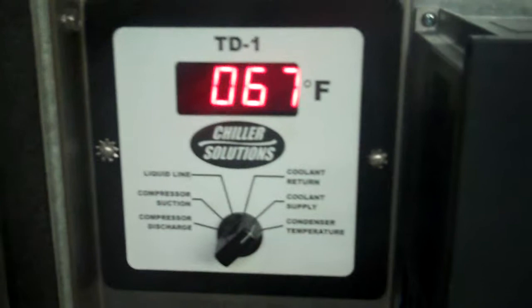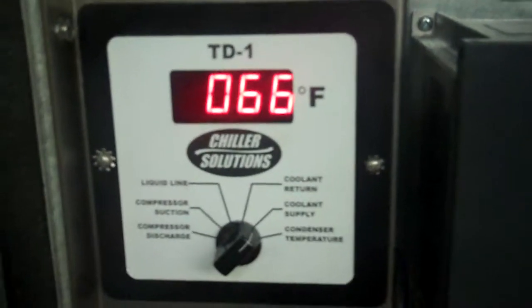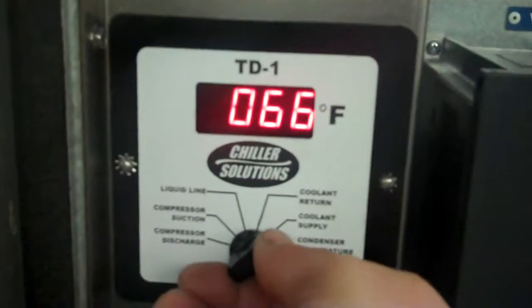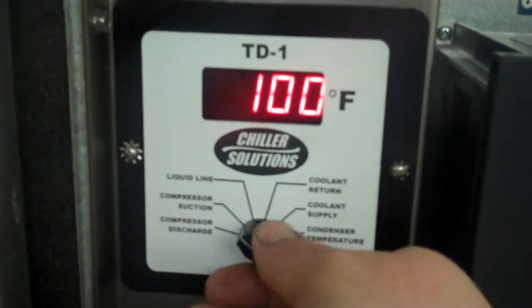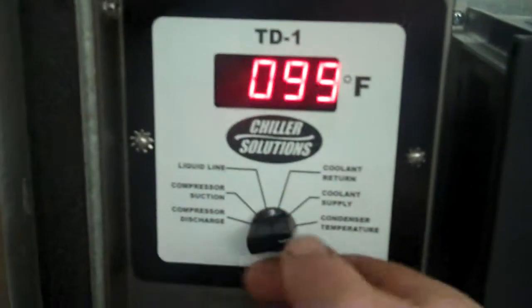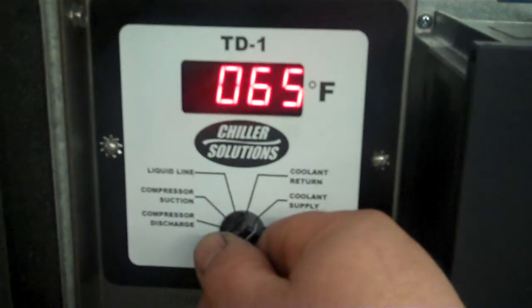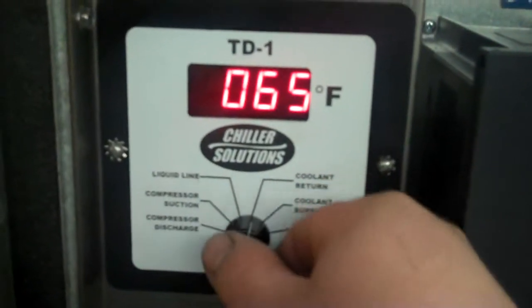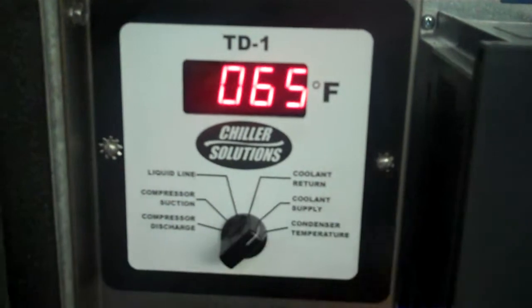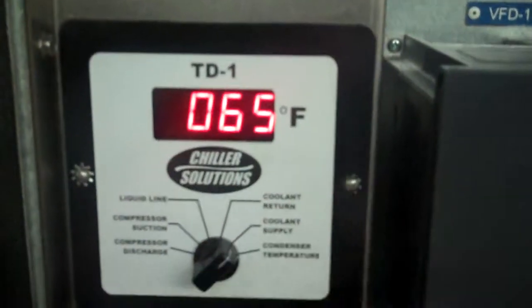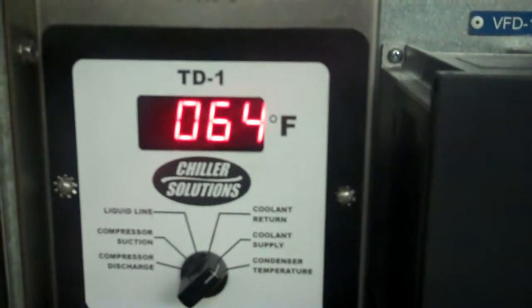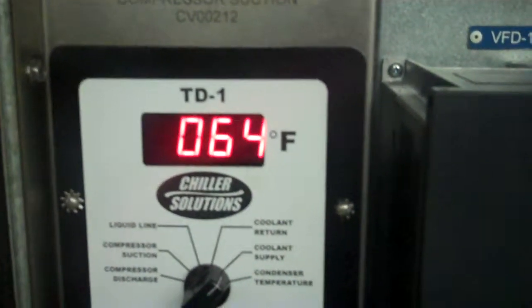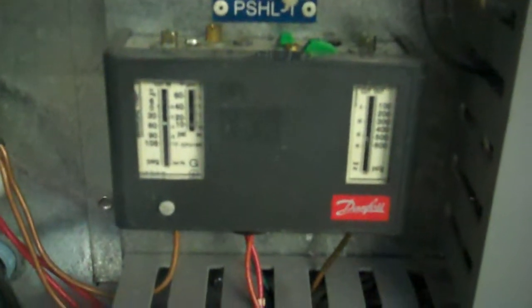This readout here gives us a bunch of things, most of which is helpful for an HVAC technician to monitor, like liquid line temperature, compressor suction, condenser temperature. But the two big ones here are coolant supply and coolant return. The coolant supply right now is already chilled down to about 65 F and dropping fairly rapidly. Right here is where we have the pressure switches, the high and low pressure switches for the refrigerant. And again, this is our VFD drive for the fans.